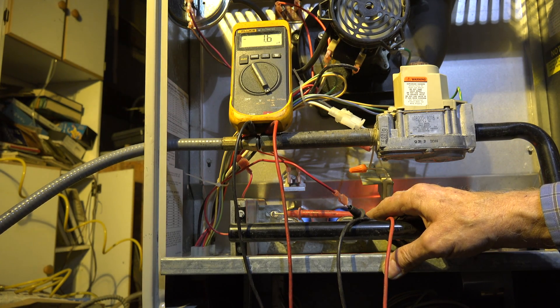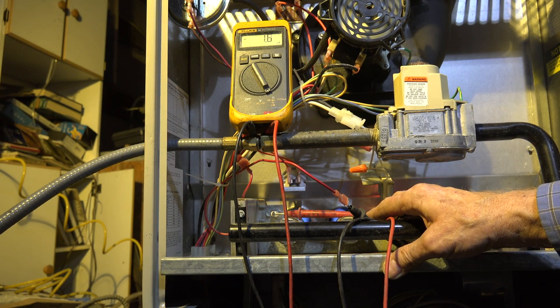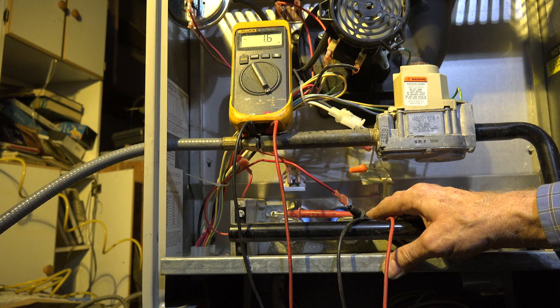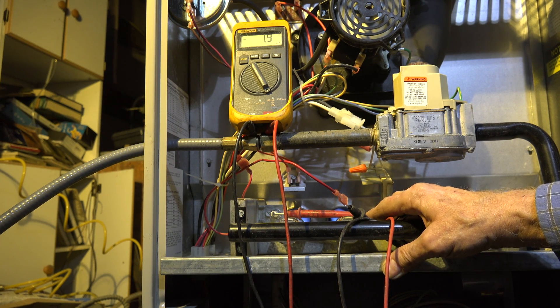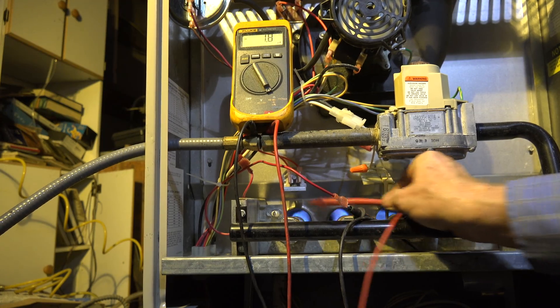Okay see we're reading about 1.5 which is kind of minimal. It is a clean flame rod. So there's actually power going through it. Now let's take it loose.